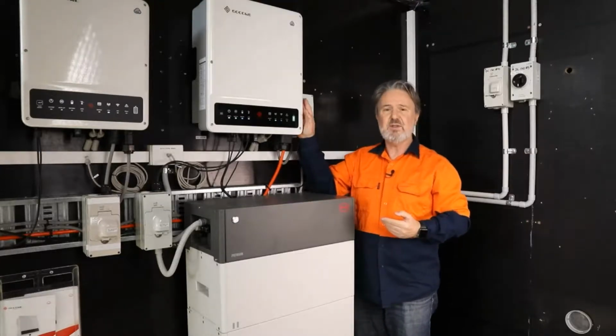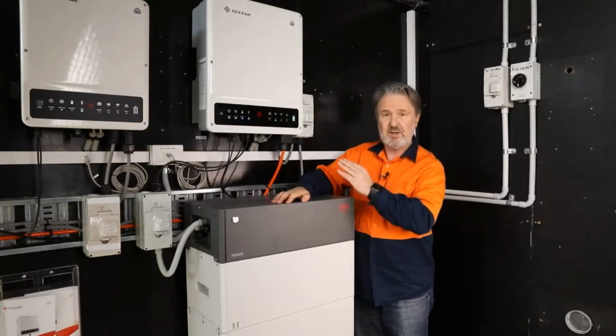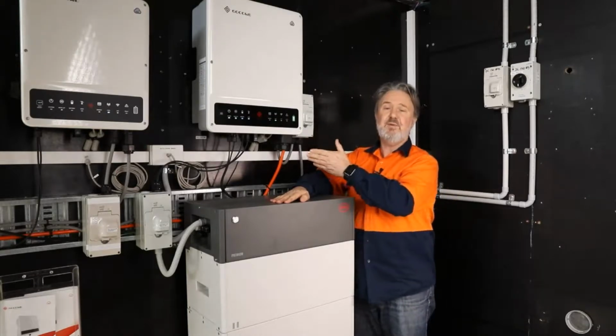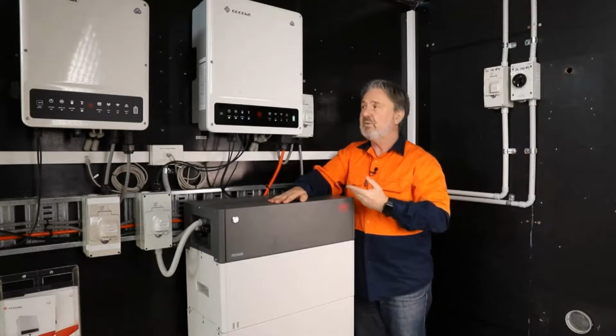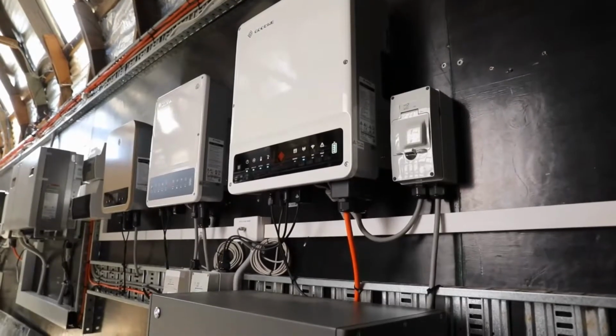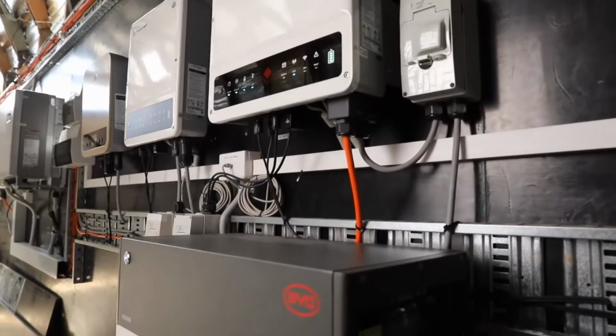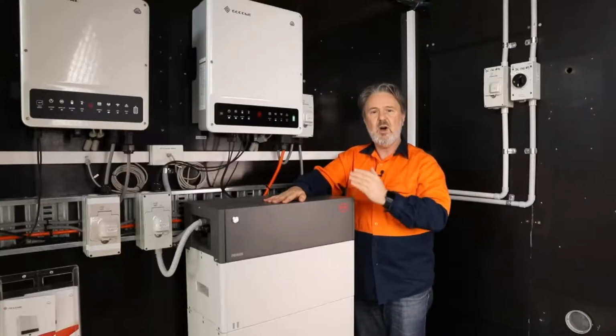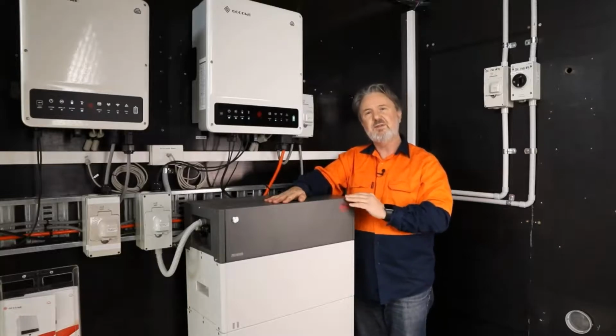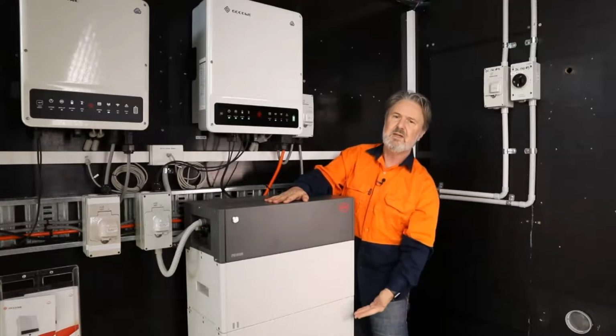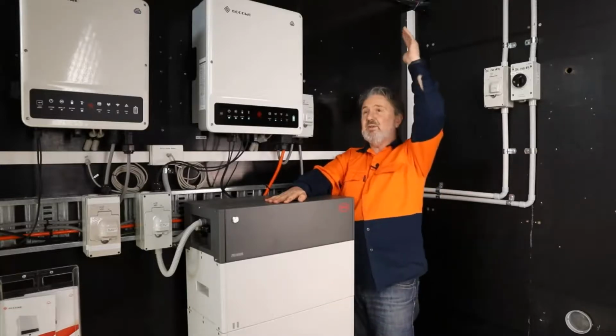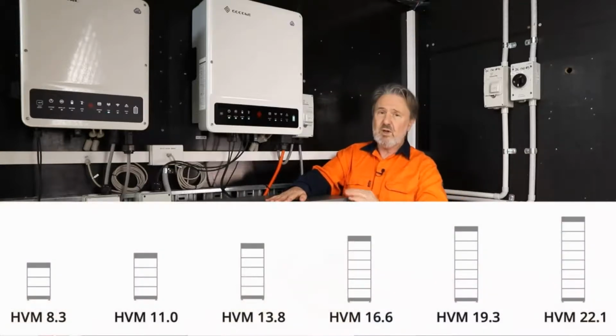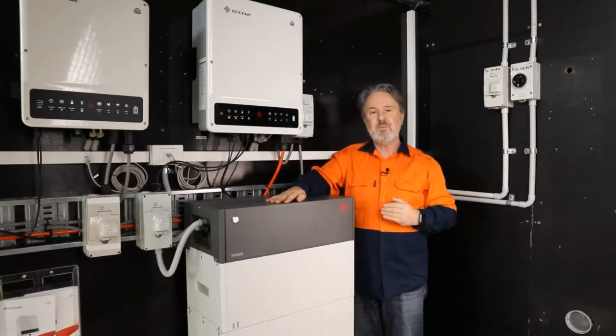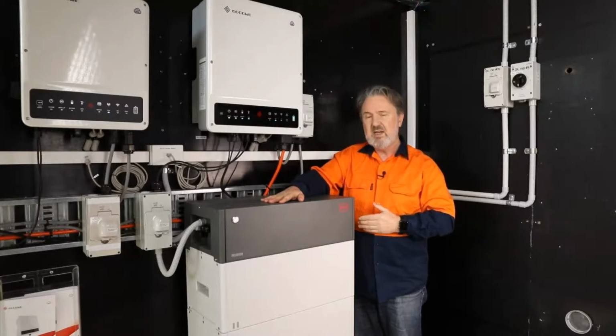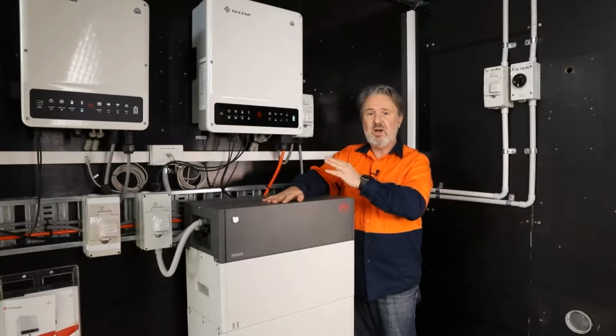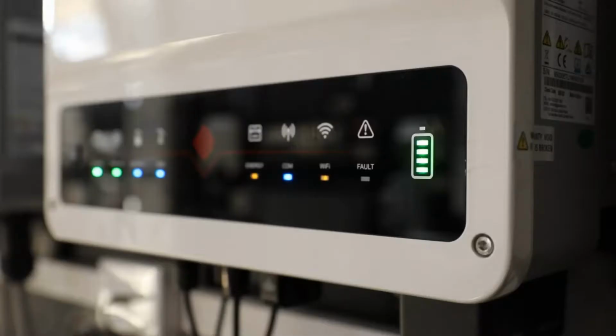Now the ET series, which is the 3-phase storage inverter, comes in several sizes - this is the 5 kilowatt unit up to the 10 kilowatt unit in the same form factor, so they're a very compact 3-phase hybrid inverter. It can also be installed as grid connect only, adding the BYD battery or other compatible battery systems with the GoodWe ET. So things that are great about the ET are the wide battery voltage range from 180 volts to 550 volts, which suits the BYD approach, a stackable battery module. You can have, I think 3 is a minimum, up to 8, which is 22 kilowatt hours of storage, making for a very tall battery, but you can have multiples in parallel as well.